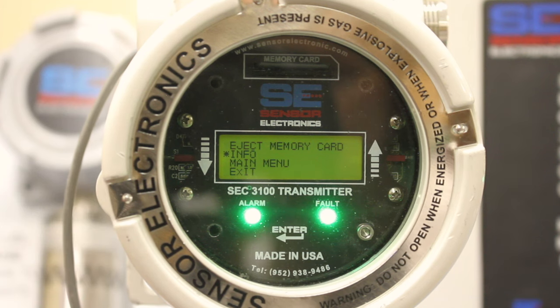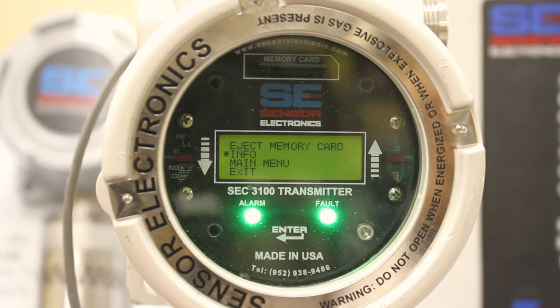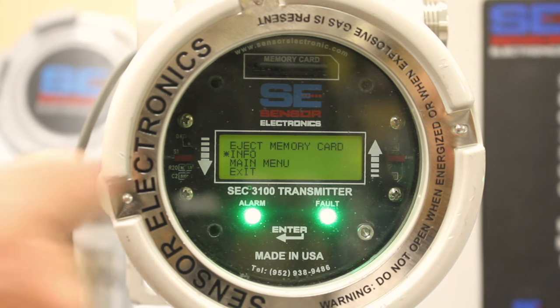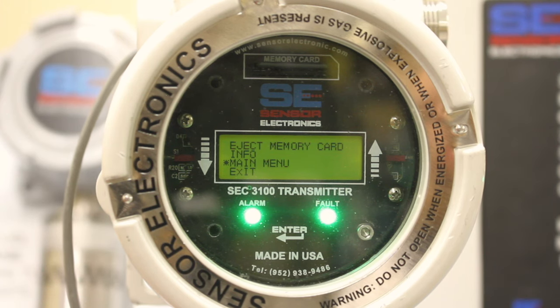The next menu down is Information. What that one tells you is just the serial number of the unit, the rev of software that it's in, and to get back out, go to Enter. The next one is the main menu structure. To enter that, the first one is Calibration. This is where you can calibrate the sensor.